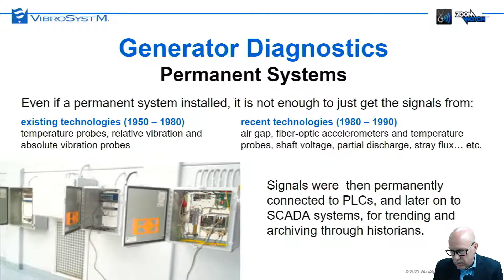So all these signals were permanently connected to PLCs and later on to SCADA systems for trending and archiving through historians. But this only warns the operators if the variations, whether they're increases or decreases, are present, and establishes limits of operation. It doesn't allow for a comprehensive in-depth analysis. If thresholds are breached, experts still need to be called in to investigate. So this approach is considered by many as monitoring, but for us, we call that trending.